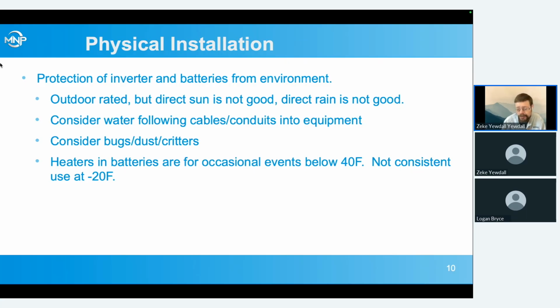I see the heaters as good for, like I said, milder climates where most of the time it's 40 degrees and above, and you'll have a cold snap and it might freeze and get down into the 20s, but it's not going to stay there for weeks on end. Also, in a lot of the garage installations in colder climates, it's an insulated garage. It's not a heated garage, and sometimes someone forgets and leaves the garage door open, or you get really cold and it gets down below freezing inside that garage. That's an appropriate use of the heaters for when occasionally it's getting down below freezing in there, or if you had an emergency event like someone forgetting to close the garage door overnight, they could pull off the grid, keep those batteries warm, and you wouldn't have frozen batteries.